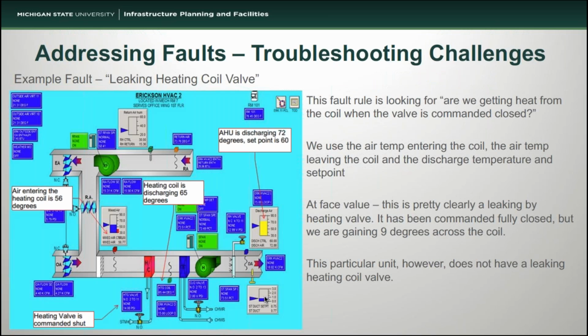An example of that is the slide that I jumped to earlier, this leaking heating coil valve. The assumption we make here is that we have a fault that triggers. As you look at this, this is a typical H pattern air handler. You don't really need to understand it in detail, but you should see that the air coming into the heating coil is 56 degrees. We see that the heating valve is commanded shut, so it shouldn't be heating at all right now. You can also see that the discharge of the heating coil is 65 degrees, and we're trying to meet a 60-degree set point to the space, but we're actually getting 72 degrees. So at face value, it's easy to look at this graphic and say, oh gosh, that heating valve's leaking by, we need to replace it.